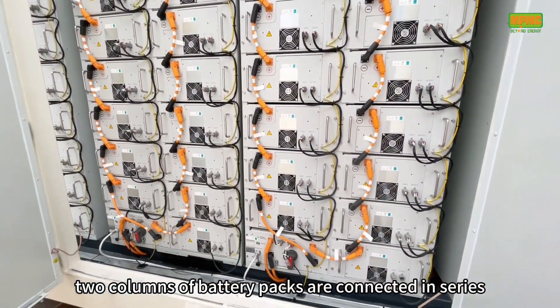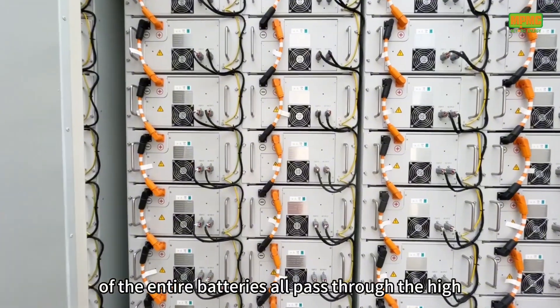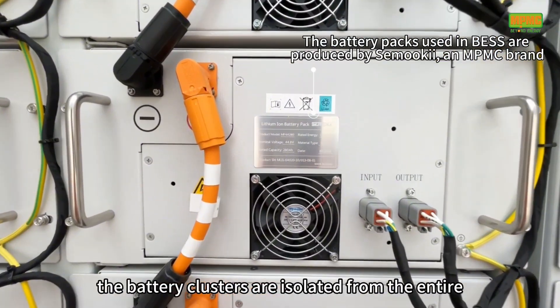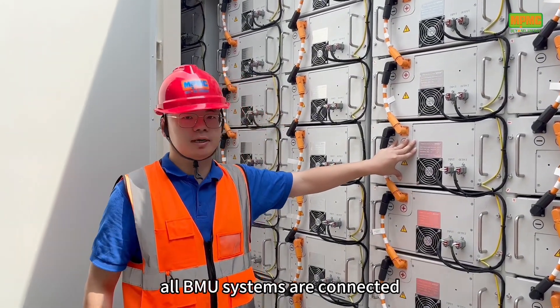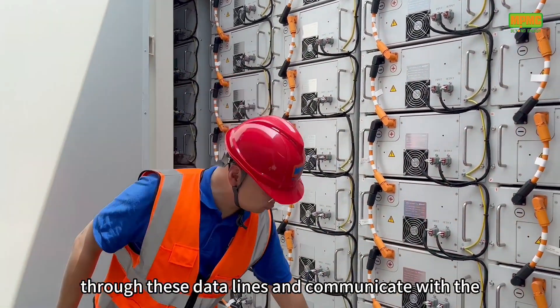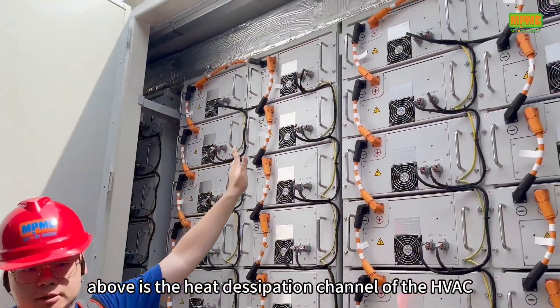These are the battery clusters in the BESS. Two columns of battery packs are connected in series with their positive and negative poles to form a battery cluster. The input and output of the entire batteries all pass through the high voltage box. When a high voltage box is cut off, the battery clusters are isolated from the entire system. Each battery pack is equipped with a BMU system. All BMU systems are connected through data lines and communicate with the control module in the high voltage box to easily send instructions.